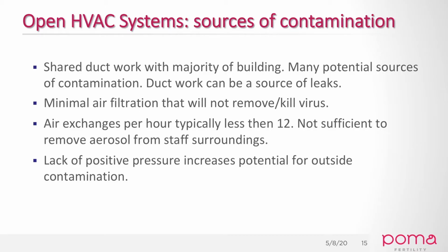What about open HVAC systems? They tend to share ductwork with the majority of the building, so there are many sources of contamination. Since the ductwork isn't sealed for high pressure, it can leak. There's minimal air filtration, so viruses aren't killed. Air exchanges are typically less than 12 per hour, not sufficient to remove aerosol produced by lab staff. These rooms also tend to lack positive pressure, so outside air can easily enter the lab each time a door opens and closes.